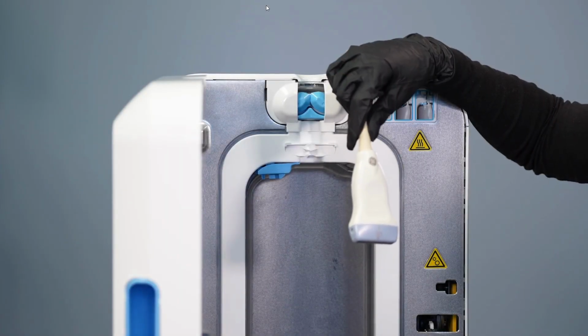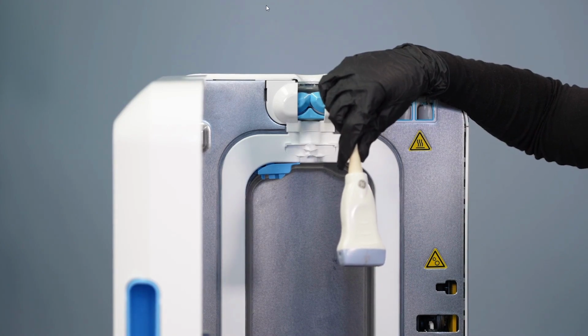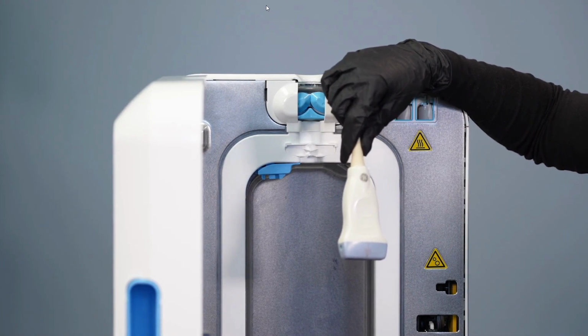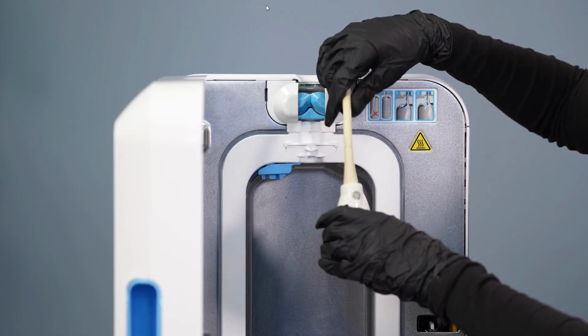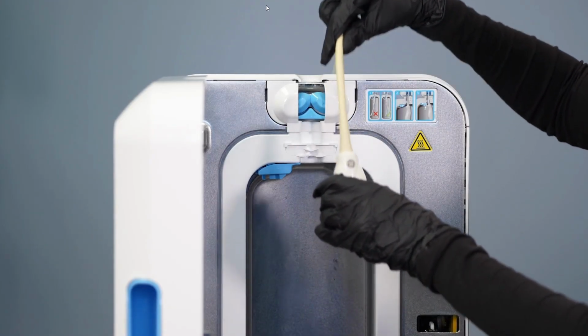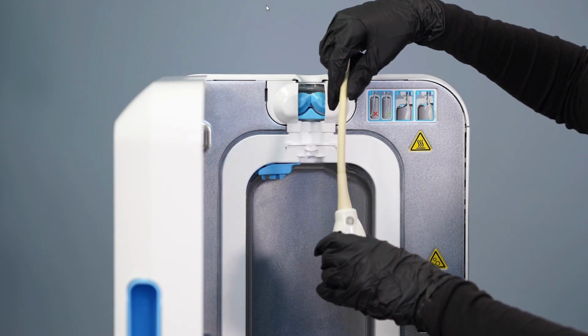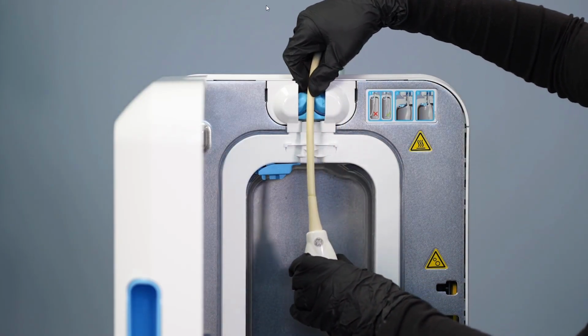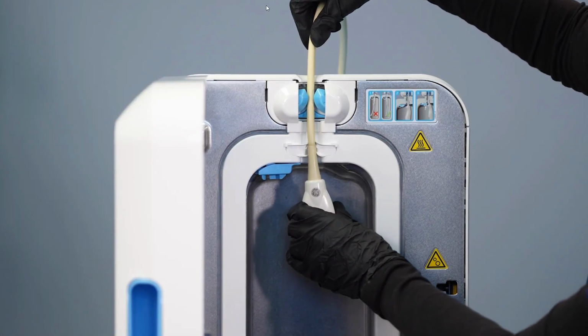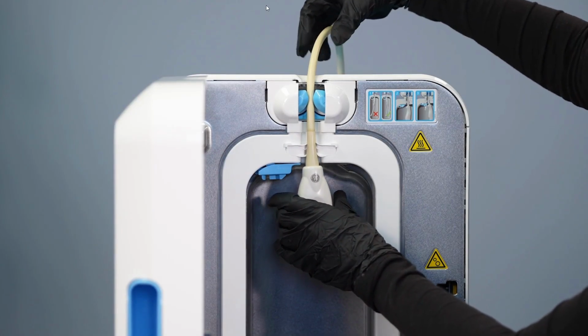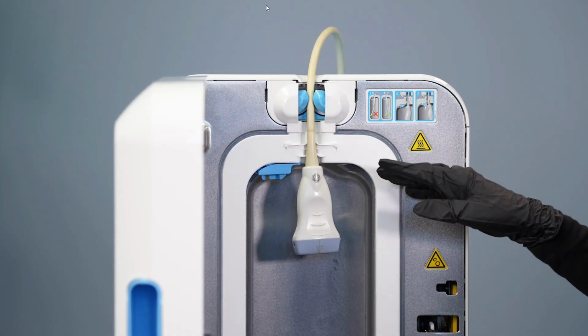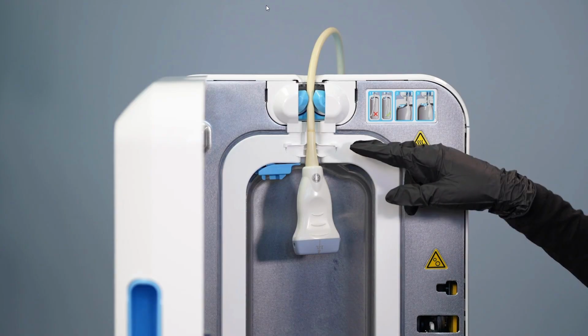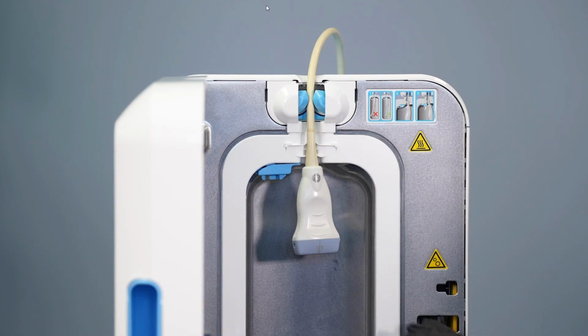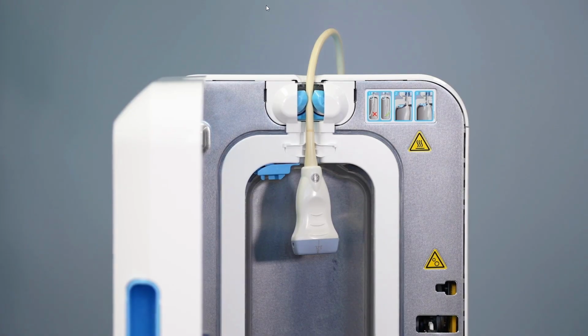When inserting an external probe into the chamber, you want to use a two-hand technique, one hand on the probe, the other on the cord itself. You can push the cord into your cable clamp starting low down in the chamber and gently glide upwards. Your strain relief should be resting within the white seals. The probe should be flush with the chamber without touching the chamber walls. Probe should always stay above the embossed line at the bottom of your chamber.